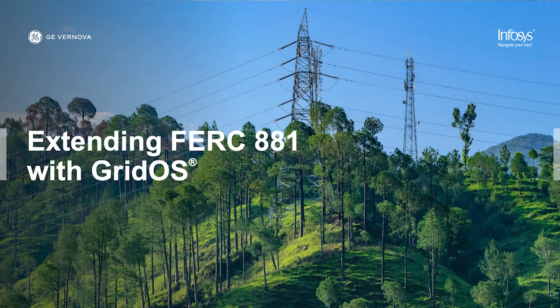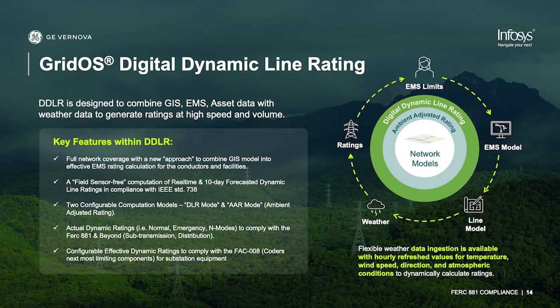So looking at another application, if we want to extend the FERC 881 with our Grid OS application, our grid orchestration software, that's our microservices-based applications. Our digital dynamic line rating is based on Grid OS and microservices. Essentially, we're able to unlock capacity on your entire footprint with the software solution without installing any traditional hardware-based sensors out on your transmission lines.